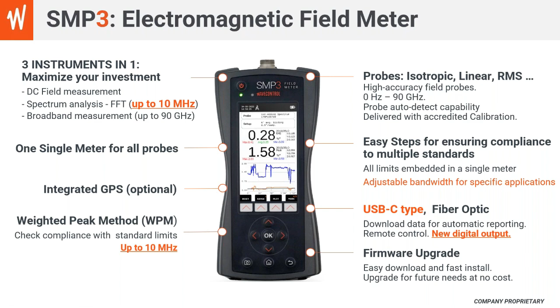Then also the device is firmware upgradable. So for example, if there's a new standard, if there is a new limit which has been included, if there are also new features, maybe the device has also been improved, all these are done via firmware. All you need to do is download the new firmware and then update it to your device. So it's an easy step which you can do to have your device up to date. So all these are different things which are provided. Also, the probes which are delivered with these SMP3 meters are delivered with accredited calibrations. So you know that the instrument is certified to be able to do your assessments in different applications.